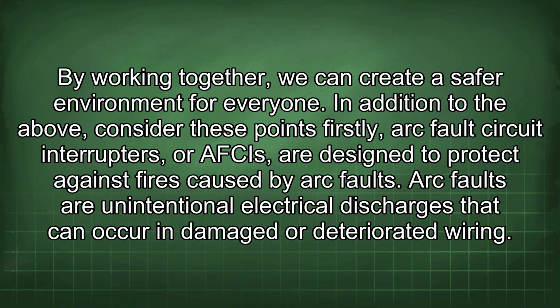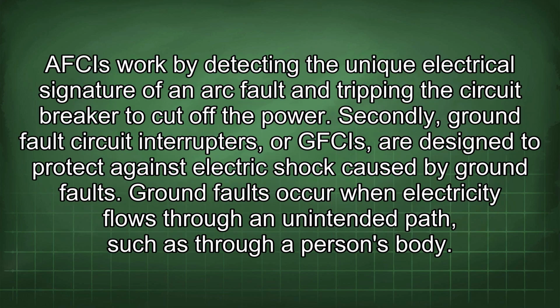Firstly, arc fault circuit interrupters, or AFCIs, are designed to protect against fires caused by arc faults. Arc faults are unintentional electrical discharges that can occur in damaged or deteriorated wiring. AFCIs work by detecting the unique electrical signature of an arc fault and tripping the circuit breaker to cut off the power.